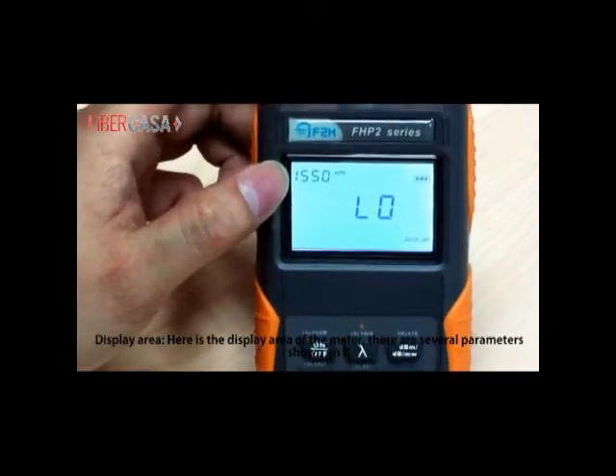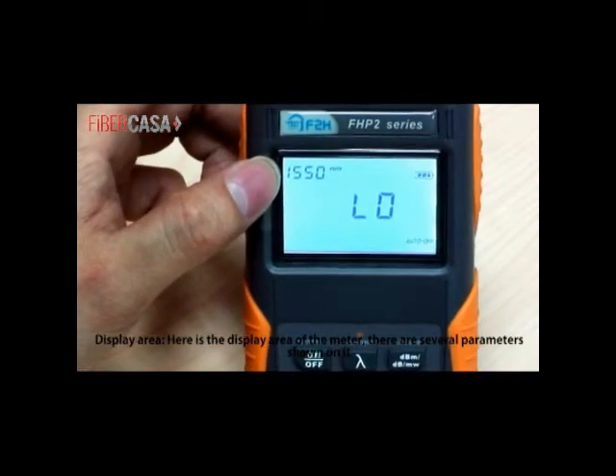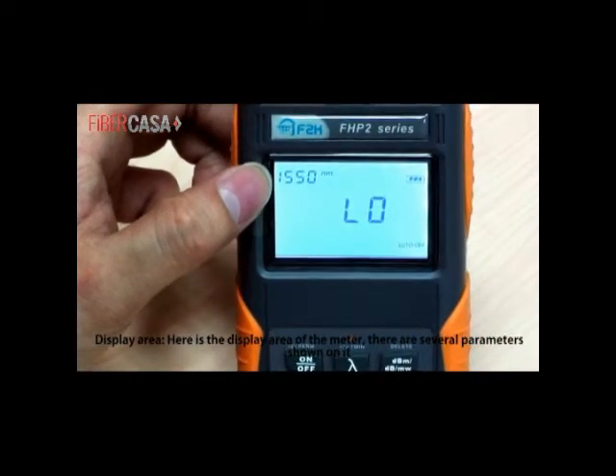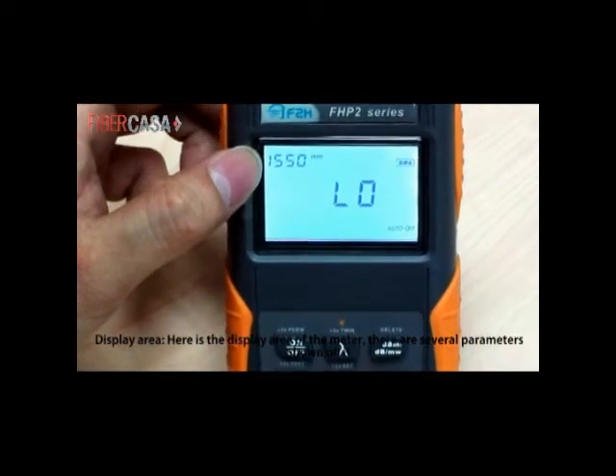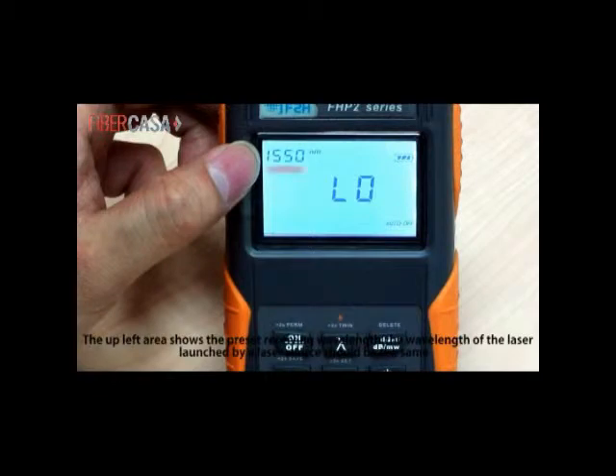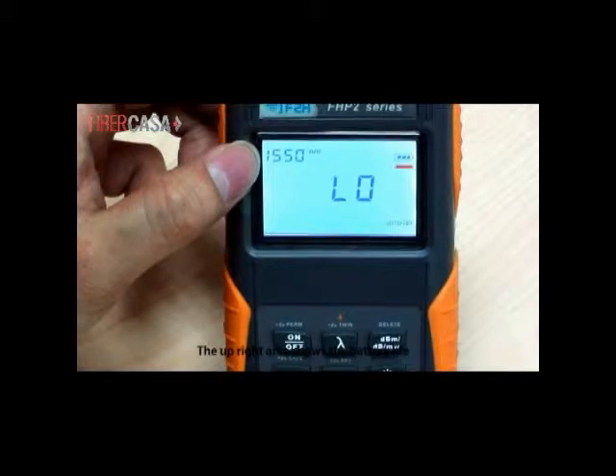Display area. Here is the display area of the meter. There are several parameters shown on it. The upper left area shows the preset receiving wavelength. The wavelength of the laser launched by a laser source should be the same. The upper right area shows the battery life. The middle area shows the input power. The down right area shows the auto power off function.